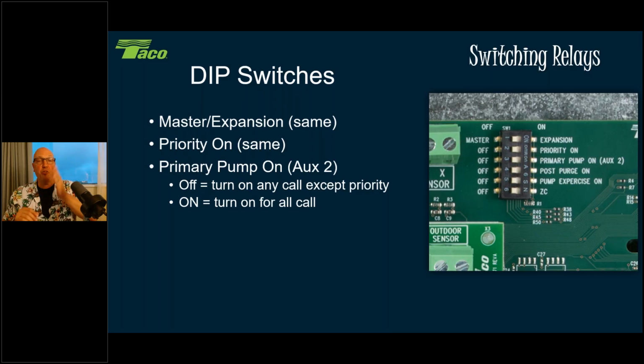If you have your indirect piped in as a zone next to your other zones, then I'm going to need to make sure that boiler pump runs when this calls so I can get the BTUs out to the boiler. So that's what we mean by on and off here, not off as in don't run, but I got to turn it off on any call and turn it on just for priority, and then back and forth. You know what I'm talking about.